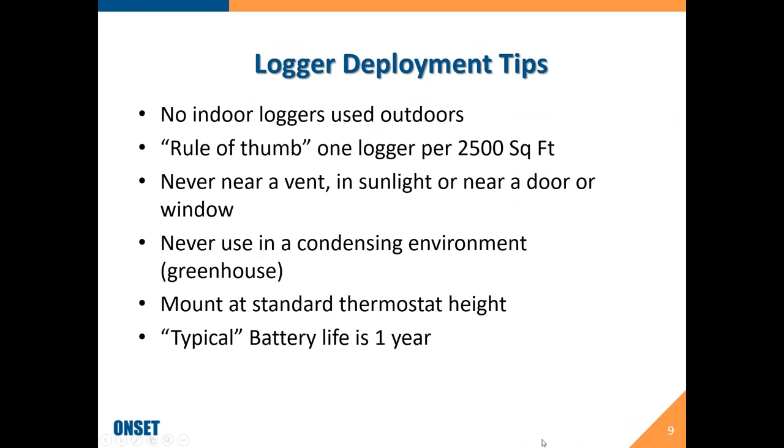Logger deployment tips. As far as using indoor loggers outdoors, that's a no-no. Indoor loggers are not protected against moisture, rainfall, that kind of thing, condensation. Never use an indoor data logger to measure outdoor temperatures. Rule of thumb for an average logger is 1 logger per 2,500 square feet. So if you're measuring a large area, you need to know whether this logger will give you accurate readings. Use 2,500 square feet as a rule of thumb.